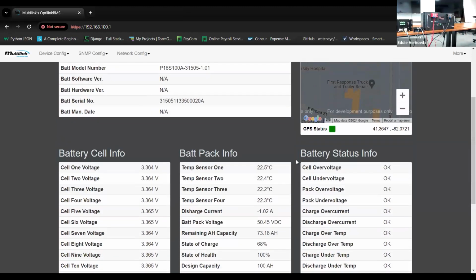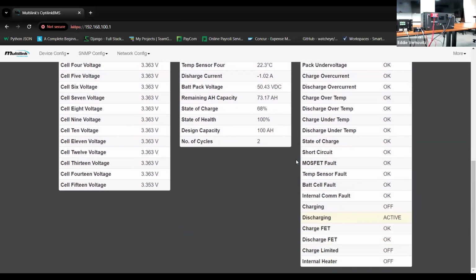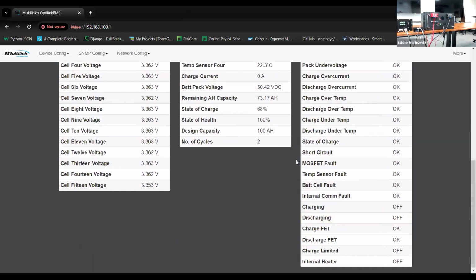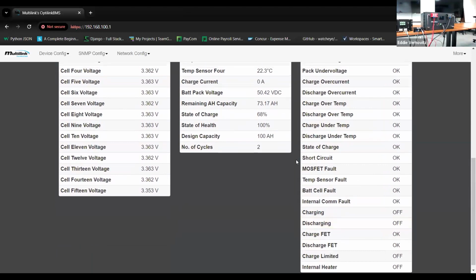So I'll place the unit back into line mode and begin the recharging state. Right now we're in a state of idle because the UPS's charger has not come up, but momentarily we should begin charging, and this table will change automatically. Here we go.